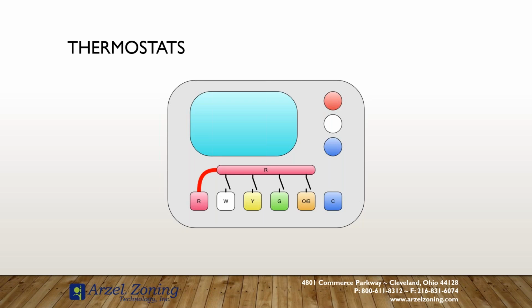So he finally called us at tech support, and we had him do the same testing he'd already done with the Arzel panel, jumpering out the calls at the panel directly. Everything responded. And then I had him test the resistance on his thermostat directly. And sure enough, the heating call, even though the thermostat said it was calling for heat, that W tested open. So he had a second bad thermostat on his truck. He went and got another one off his truck. And before he even put it on the wall, I had him test that W contact and it was open, even though the thermostat indicated it was calling for heat.